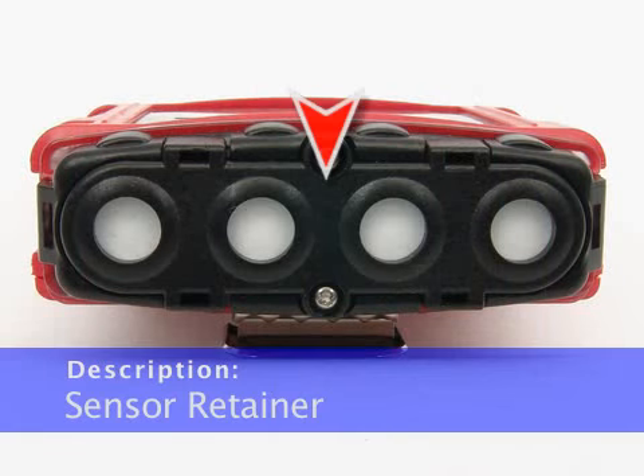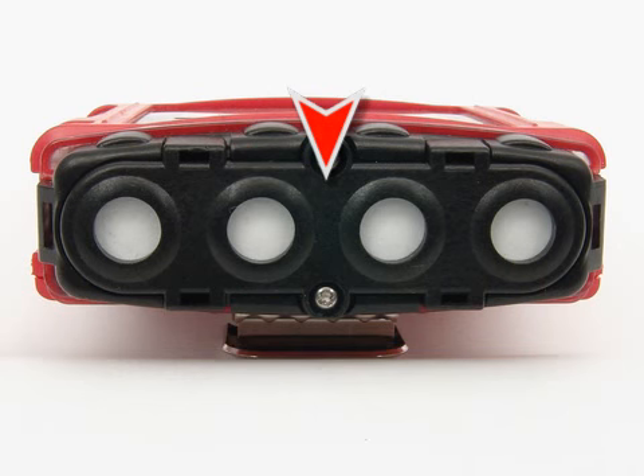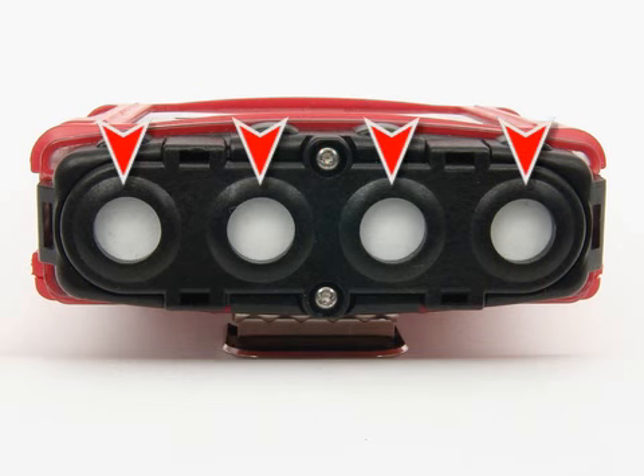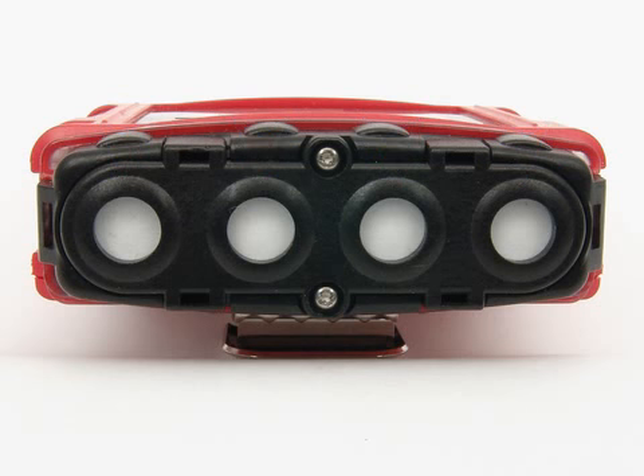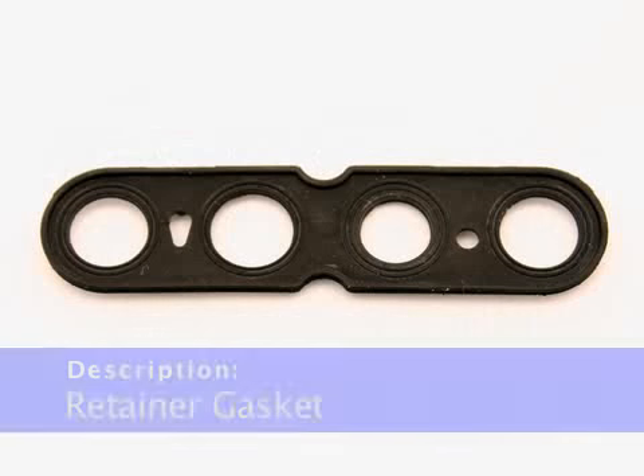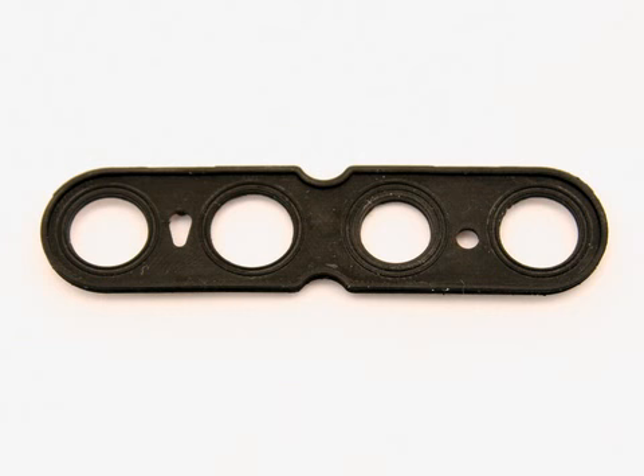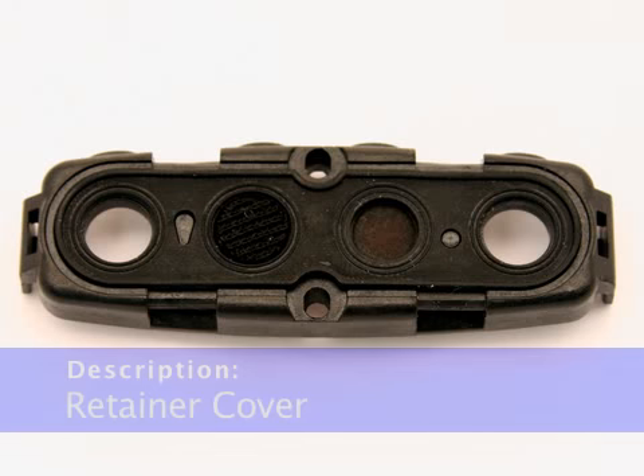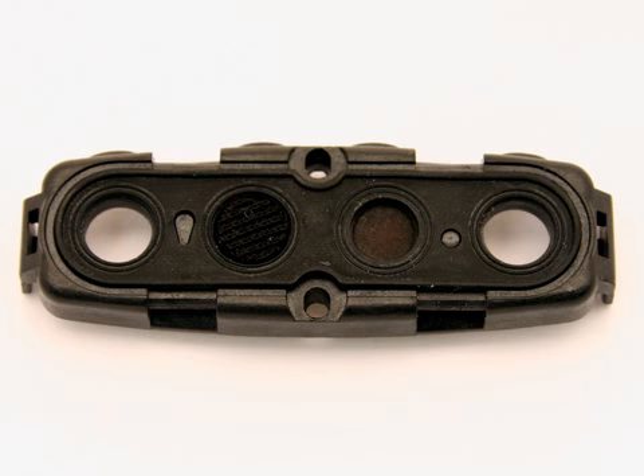The sensor retainer holds the gas sensors in place and snaps onto the bottom of the case. It has 4 diffusion ports, 1 for each sensor, and has recessed areas in it for the charcoal filter and the H2S removal filters. It also has indexing features for the sensor retainer gasket. The sensor retainer gasket seats onto the sensor retainer and seals the interface between the sensor retainer, sensor cover, and sensor cover retainer. The sensor cover retainer snaps onto the sensor retainer. 2 screws secure the sensor retainer and the sensor cover retainer to the case.